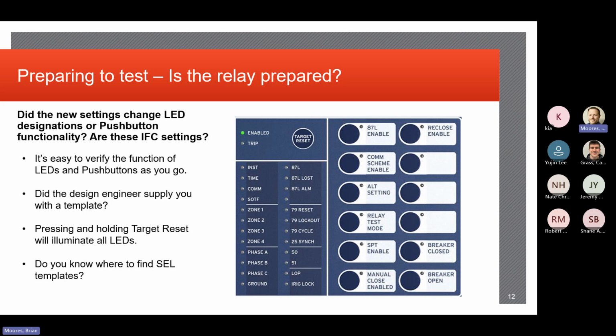A lot of times this comes through with the default labels, but SEL actually has customizable, configurable labels that you can print out and create. And it's important to make sure you're validating and verifying that it has the right labels in there as well. Because the relay engineer could have made changes to those targets and those push buttons and the LEDs associated with the push buttons. So it's always a good question to ask. And you'll notice it as you get through the logic and review that if it aligns or not. Most of the time, from what I've seen, they usually customize them.